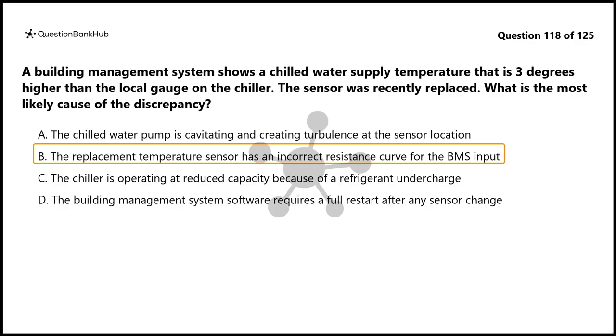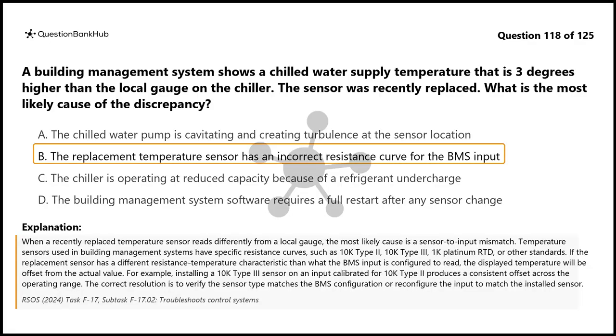The correct answer is B. When a recently replaced temperature sensor reads differently from a local gauge, the most likely cause is a sensor-to-input mismatch. Temperature sensors used in building management systems have specific resistance curves, such as 10K Type II, 10K Type III, 1K platinum RTD, or other standards.